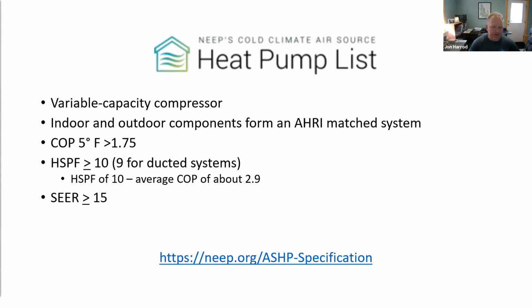Now, the performance criteria for a cold climate heat pump: they have to be able to have a COP of 1.75 or better at 5 degrees Fahrenheit. So that means that when the temperatures are down in the single digits, which is quite rare for most of the state, they are still producing almost 2 units of heat for each unit of electricity you're putting in. So we don't see that same kind of drop off in performance that we saw with the old heat pumps. They are still almost twice as efficient as electric resistance heat at very cold temperatures.